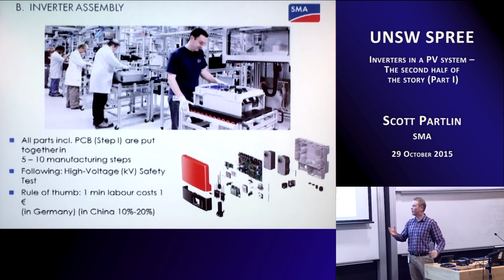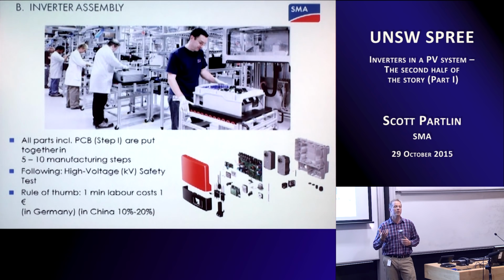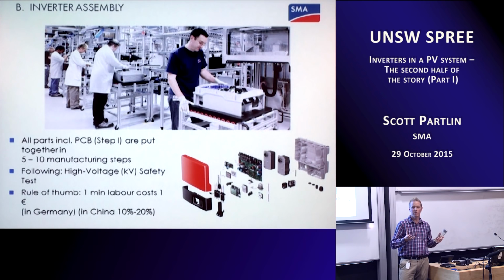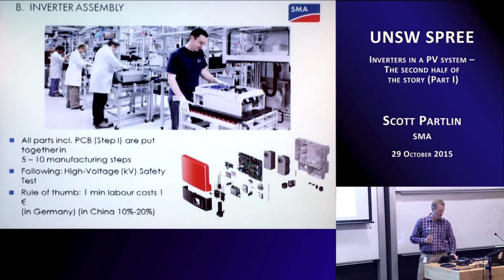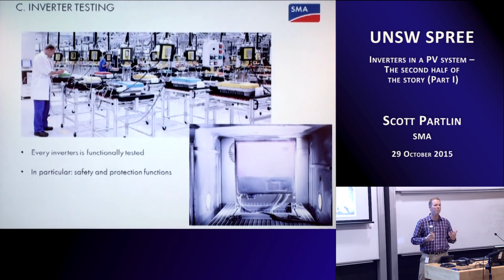Once all of the circuit boards are through the production line and manufactured, they're put together in a unit. Depending on which inverter it is, some of that will be a manual process. With the larger central inverters, the process to build the inverter can sometimes be as long as 8 weeks, whereas a smaller string inverter or a microinverter is produced in less than a day. With those smaller units, boards are automatically tested and automatically installed into the inverter. Once they've been assembled, they go through testing and burn-in to reduce infant failures.